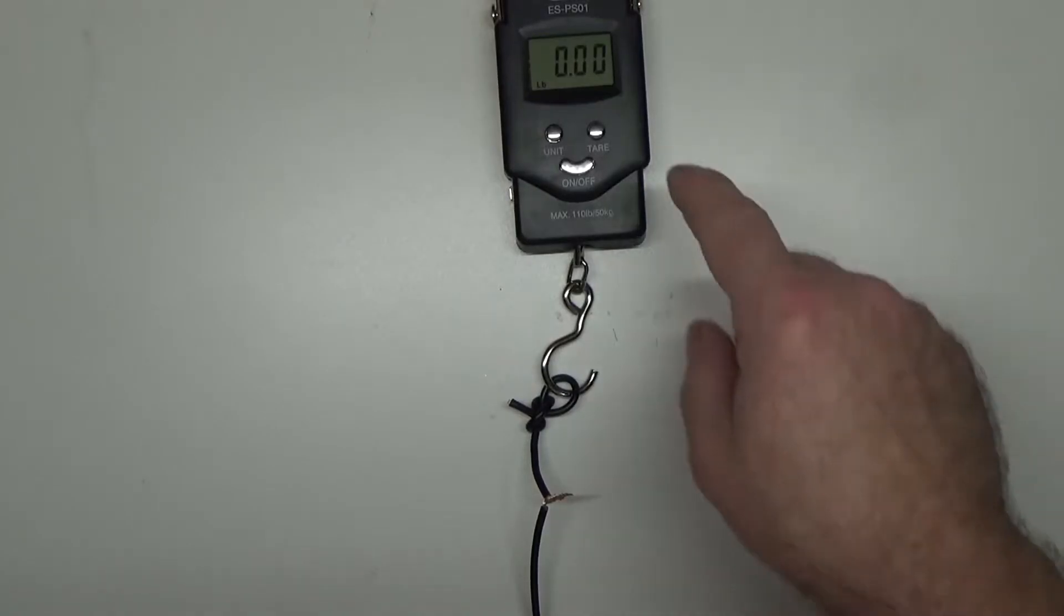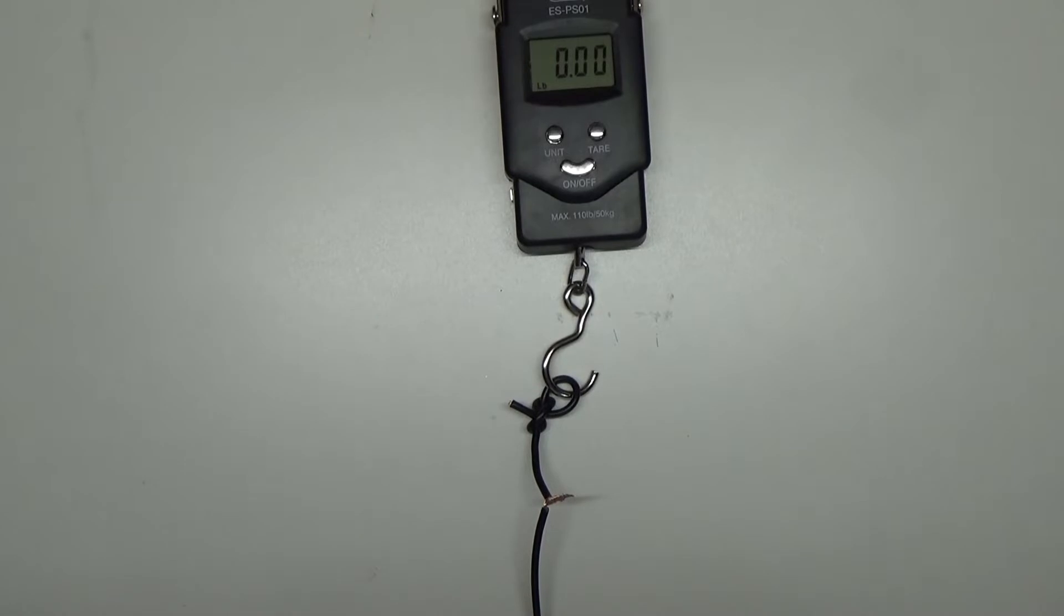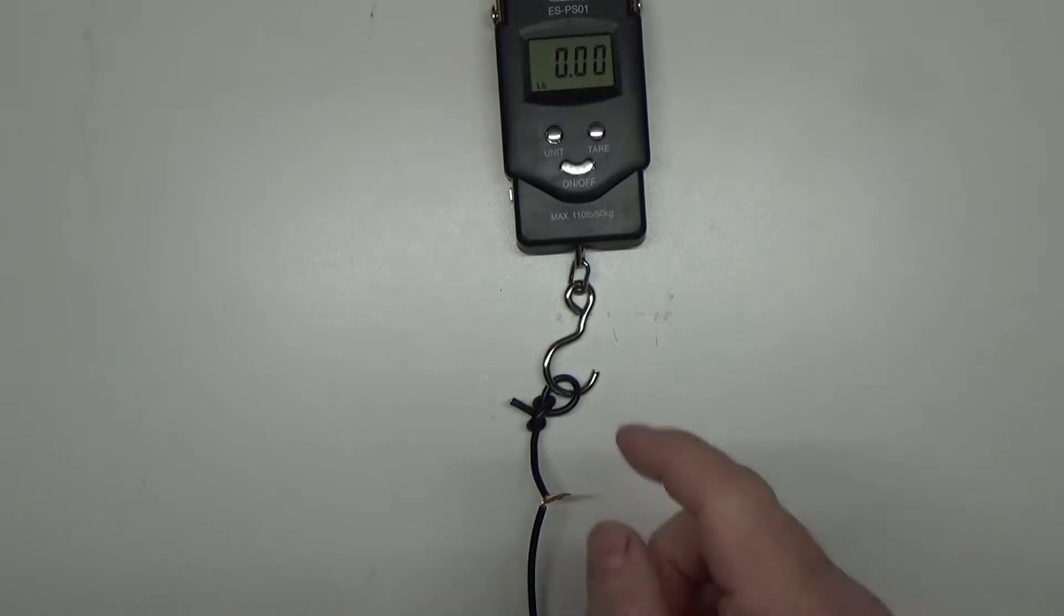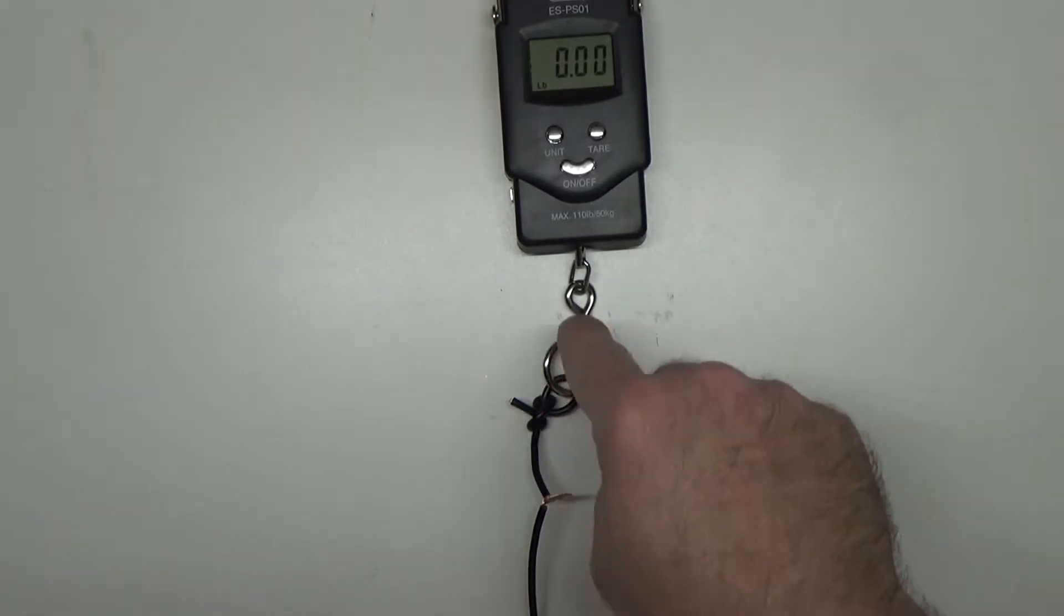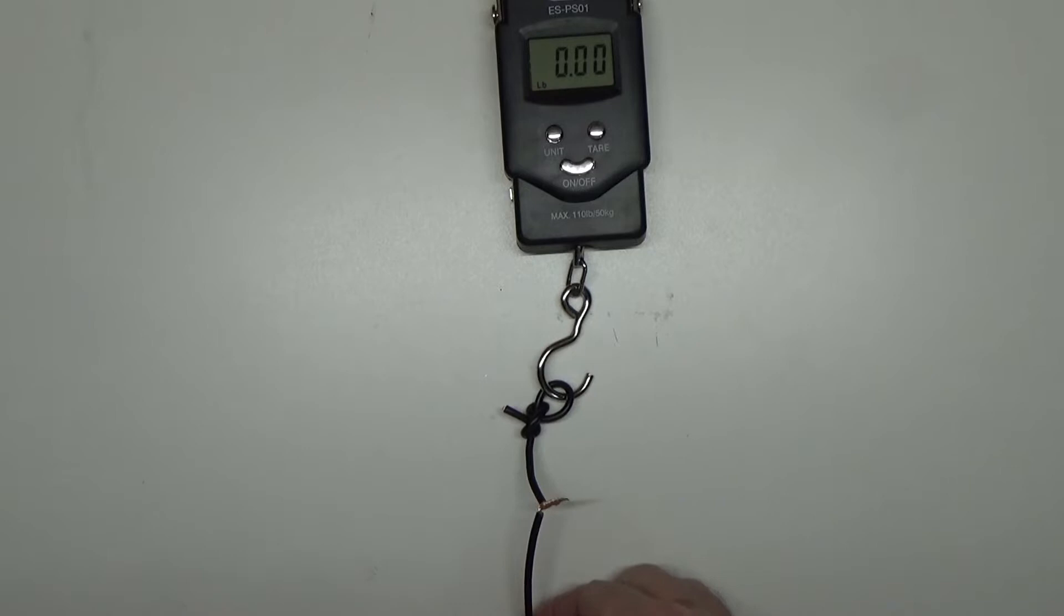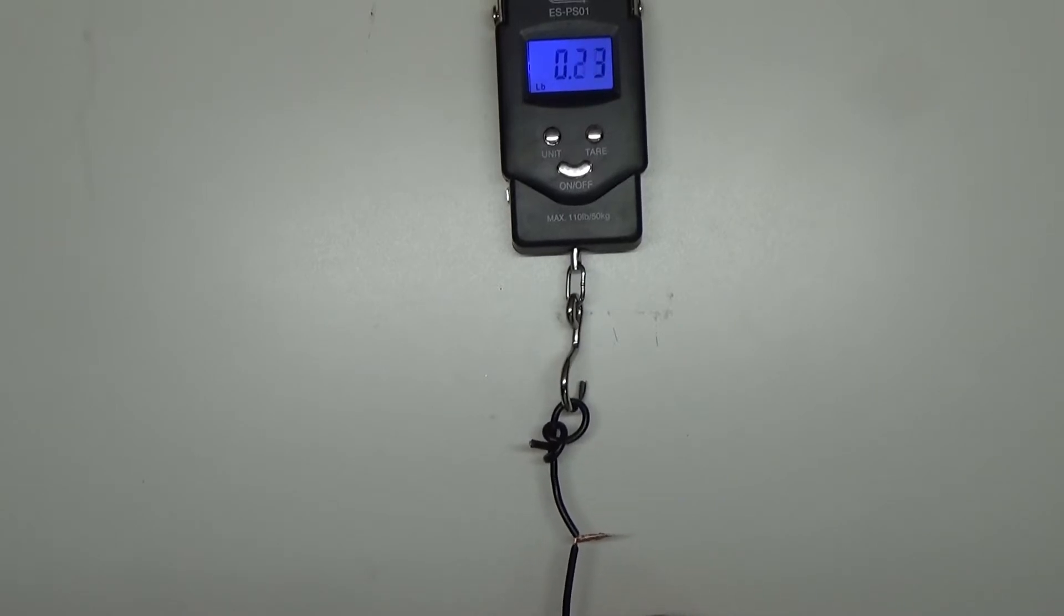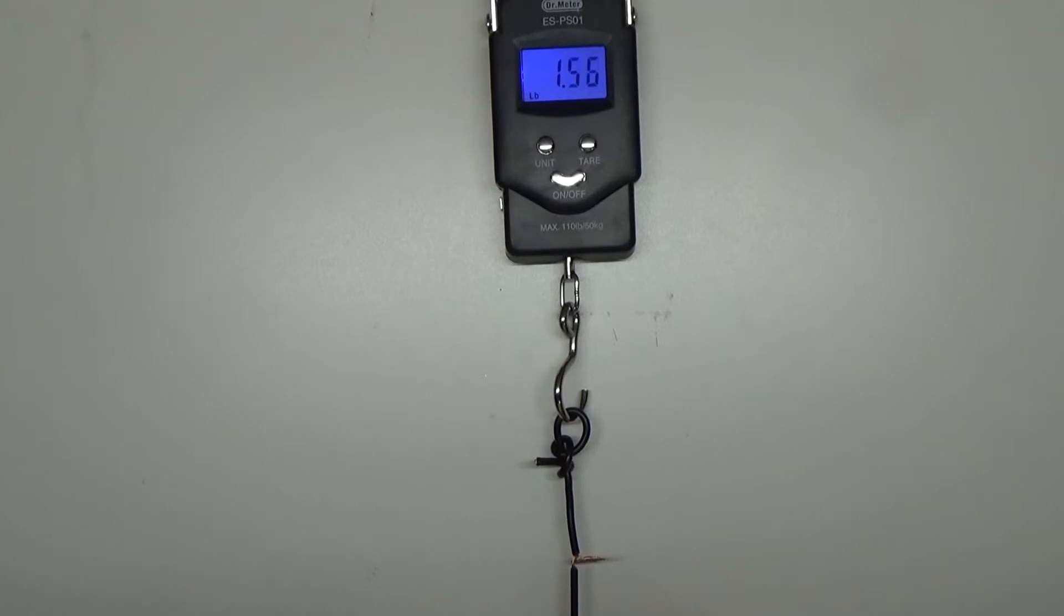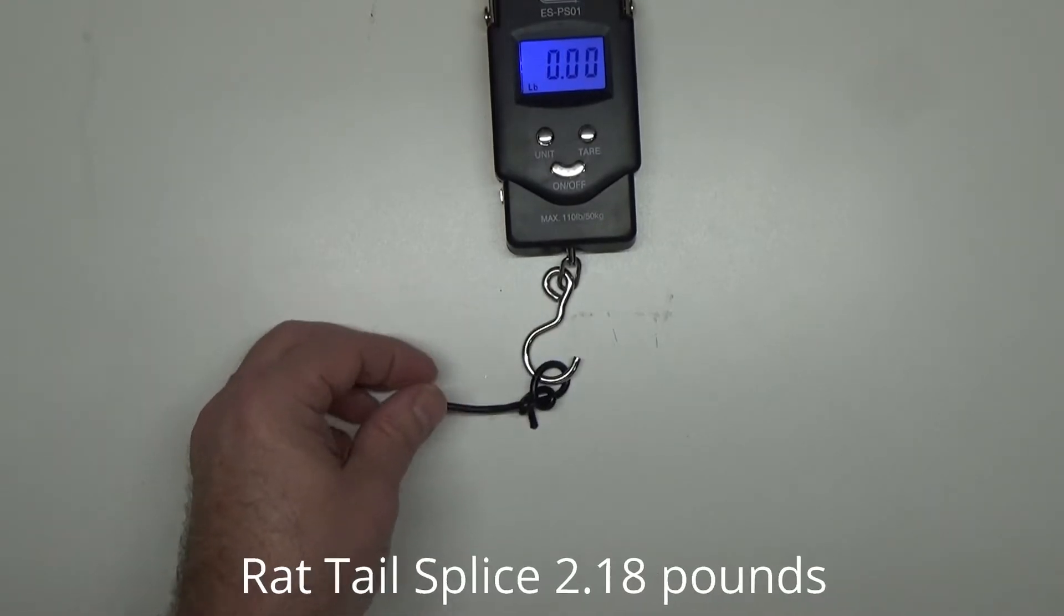What we've got rigged up here, I've got my scale tied to the top of my table here, got the wire tied to the hook. This measures in pounds. As I pull this wire, we're going to see how many pounds it takes before that wire turns loose. So this is the rat tail splice, how much does it take to pull it apart? We hit a pound. It's coming apart. Right about two pounds is where it starts separating. So about two pounds of force will separate a rat tail splice.